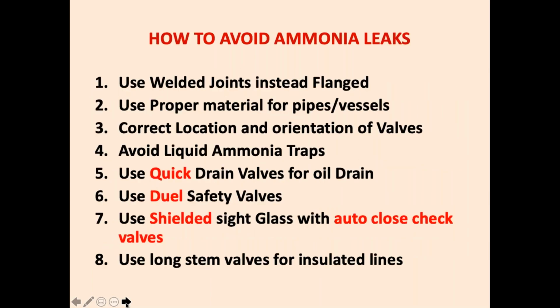How to avoid ammonia leaks? My suggestions: use welded joints instead of flanges. Wherever possible, don't use flanges. So the chances of this 22% of flange leaks are eliminated. Use proper material for pipes and vessels, a very, very important point.